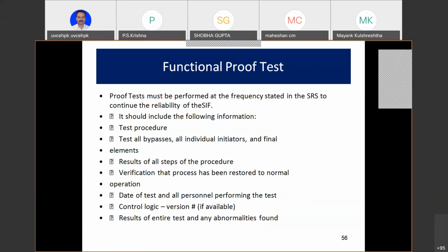And one more thing is, proof testing has to be done, as per my philosophy, which I have practiced, dynamically. You know what dynamic proof testing is? I'll take just 30 seconds to explain it. In a complex plant, you've got a turbine, you've got compressors running day in and day out. So on the 10th of October, the plant manager told me, Krishna, the plant is going to shut down. Then I made a request. I said, can I shut it down through this particular trip channel? He said, okay. So instead of using a push button or some other command to the electrical section, we simulate this particular high pressure trip by our own method and shut down the plant. That means you tested the entire system, including the calibration of the pressure switch. I've done this, because if you do only the proof testing of the pressure switch, it is possible that something could be wrong with the input to the PLC. If you do a real simulation, you can prove the point. Absolutely, very good question.